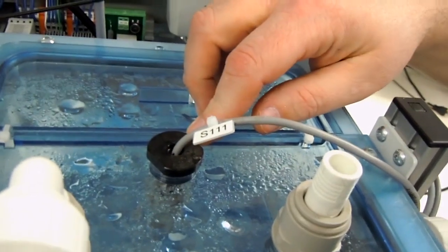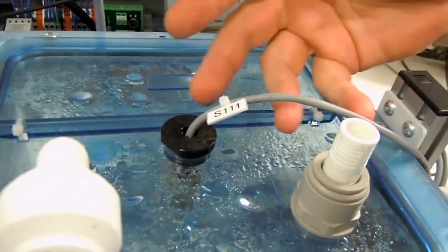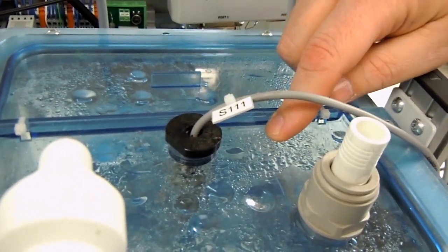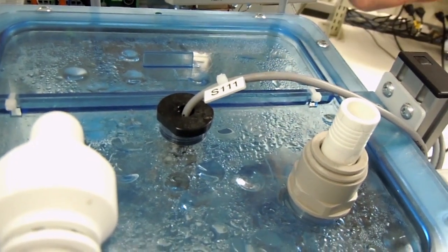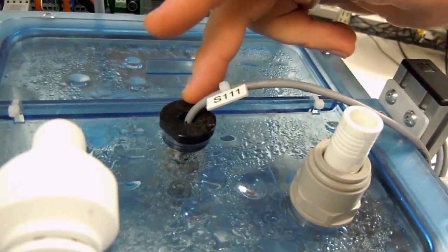The next float is up here. It's at the top of the tank. It uses a magnet and a reed switch that when that level reaches the top of the tank, the float inside there will float upwards and either turn on or off the internal reed switch. And it's really just a way to detect that you've hit the top of that tank.